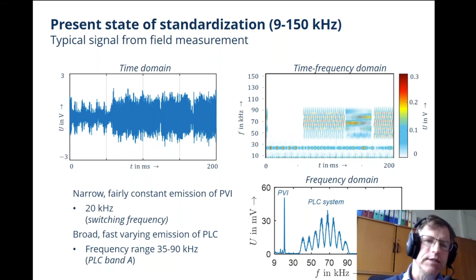Looking at the three different methods, you will immediately notice differences, especially between method B and methods A and C. B, to recall, is the new proposal in 4-30. A is the method based on 61000-4-7, and C is the CISPR method with the quasi-peak detector. For the PV emission in the middle, it seems all the methods are rather similar, at least on this logarithmic scale, but for the broadband emission and the power line communication, they differ a lot.